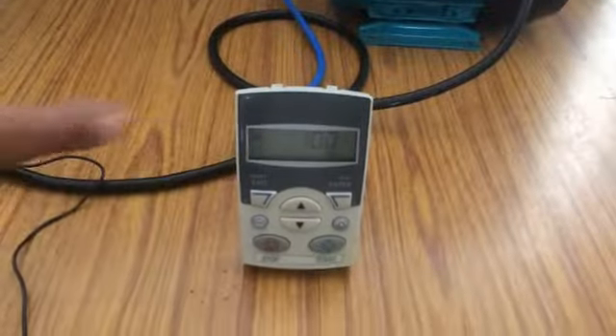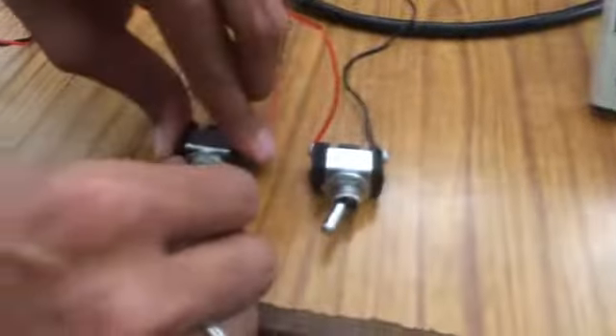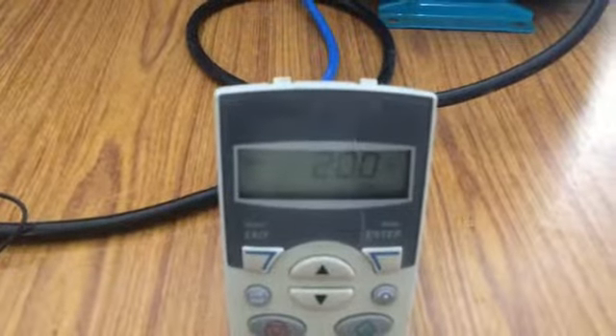By giving the reference 01, we can see the motor is running at 10 Hz. Once we change it to 10, the motor is running at 15 Hz. Finally, when we make it 11, the motor is running at 20 Hz.